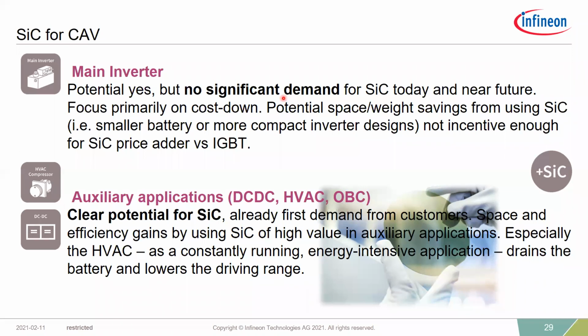That's the question, and that's why today it really doesn't bring significant value. The reason is the switching operation has to be limited to 5 kV per microsecond, meaning you have to literally slow down the silicon carbide MOSFET switching speed. When you slow it down, this increases the losses, reducing the end benefits at that operation point, so it doesn't come to a win-win situation.